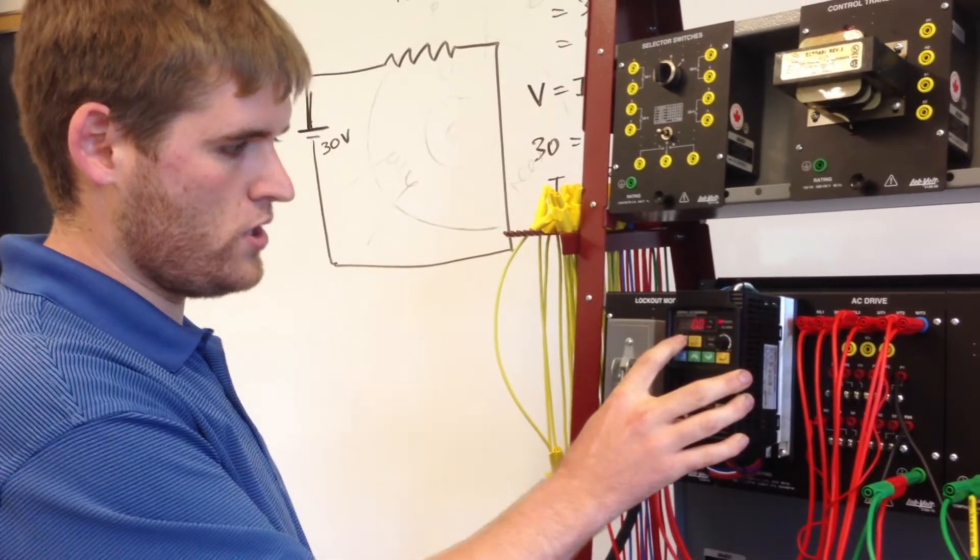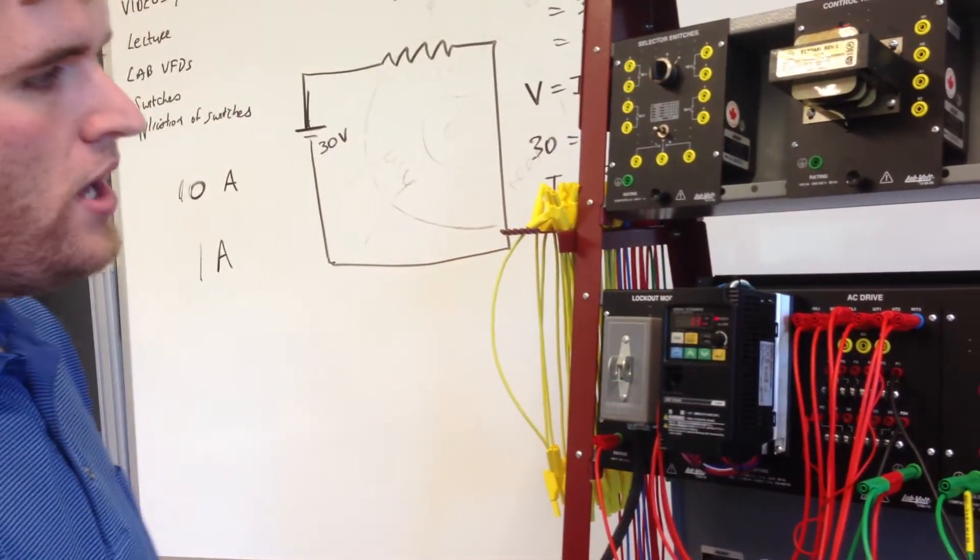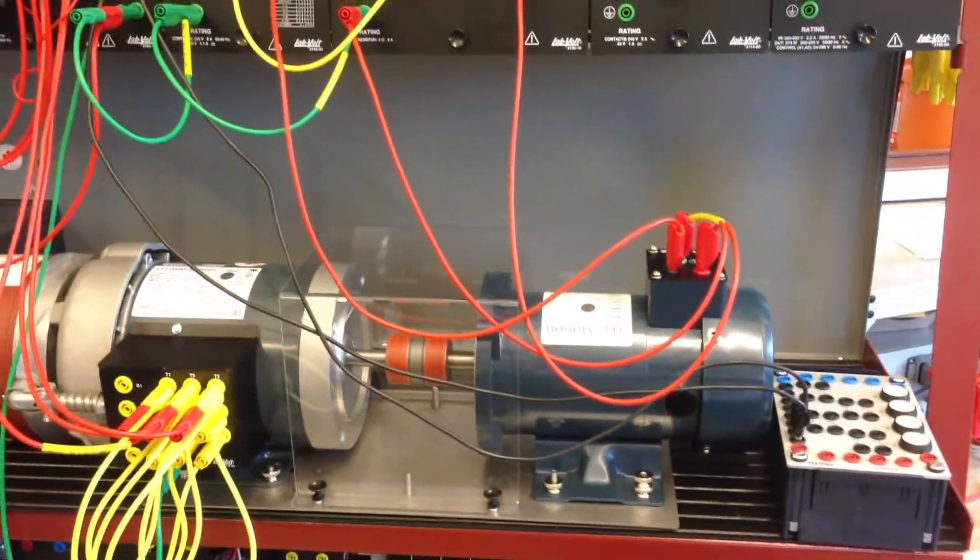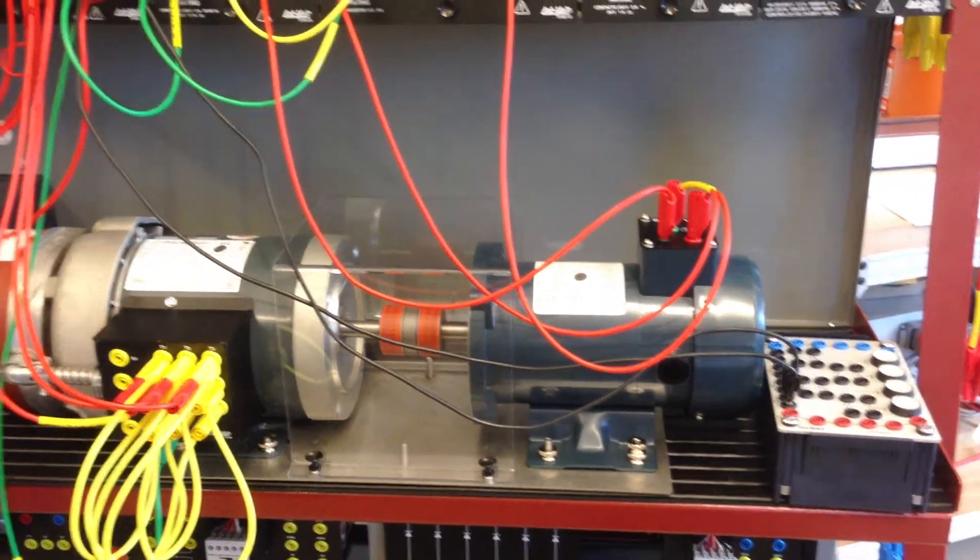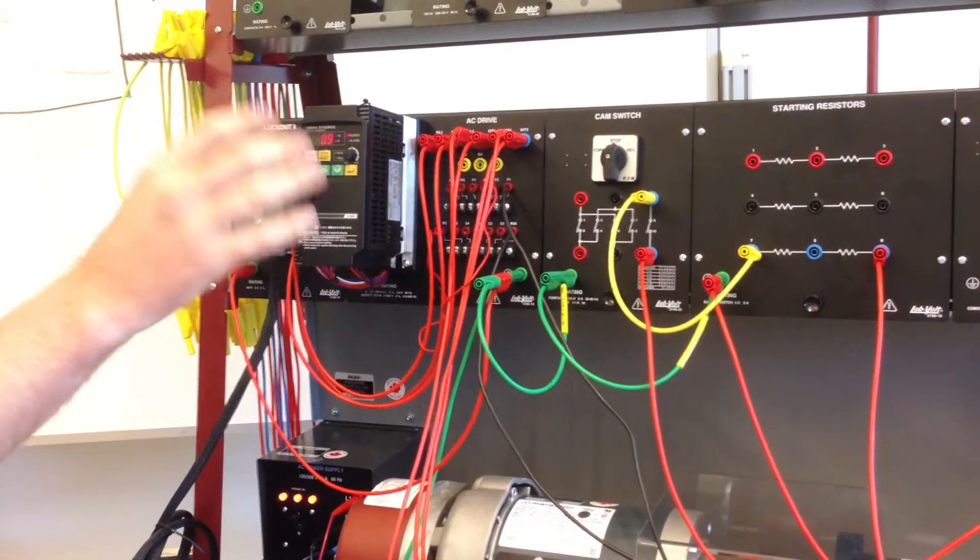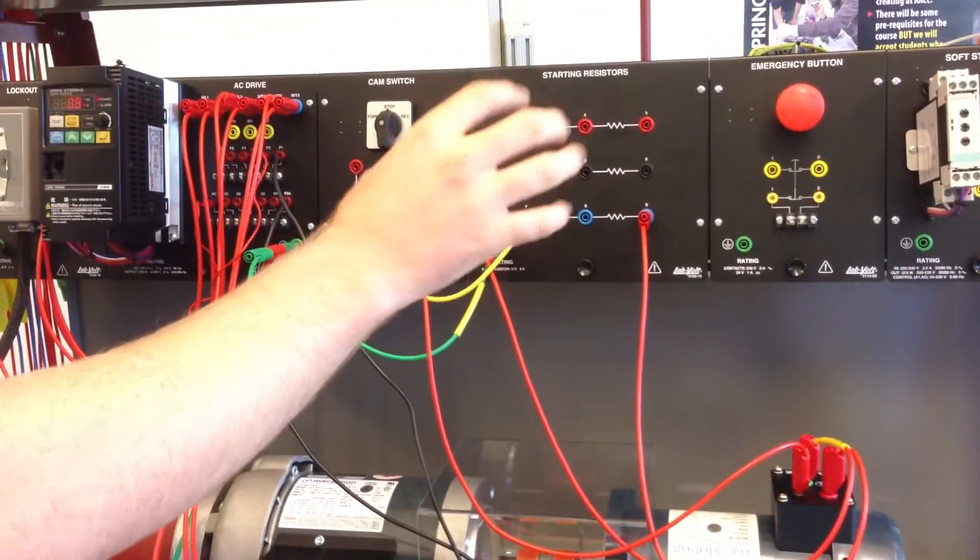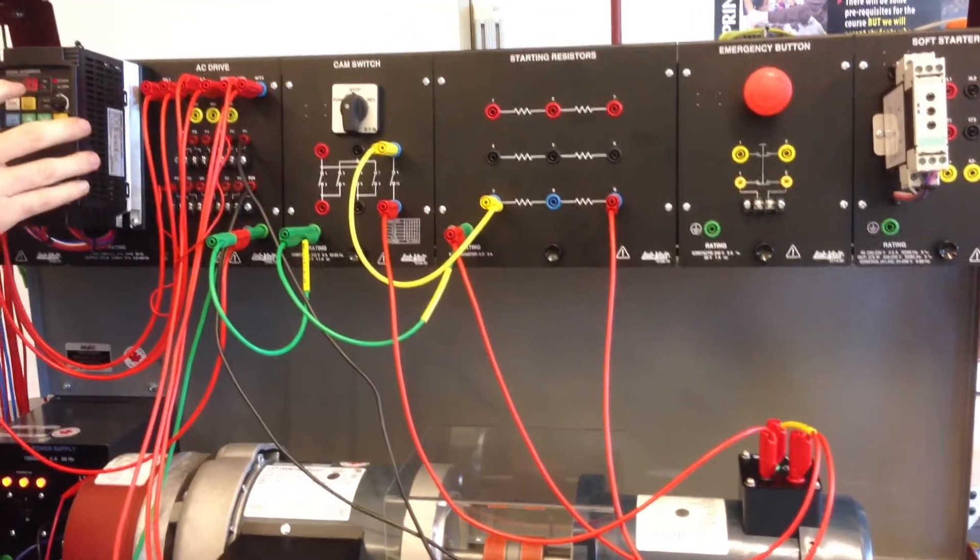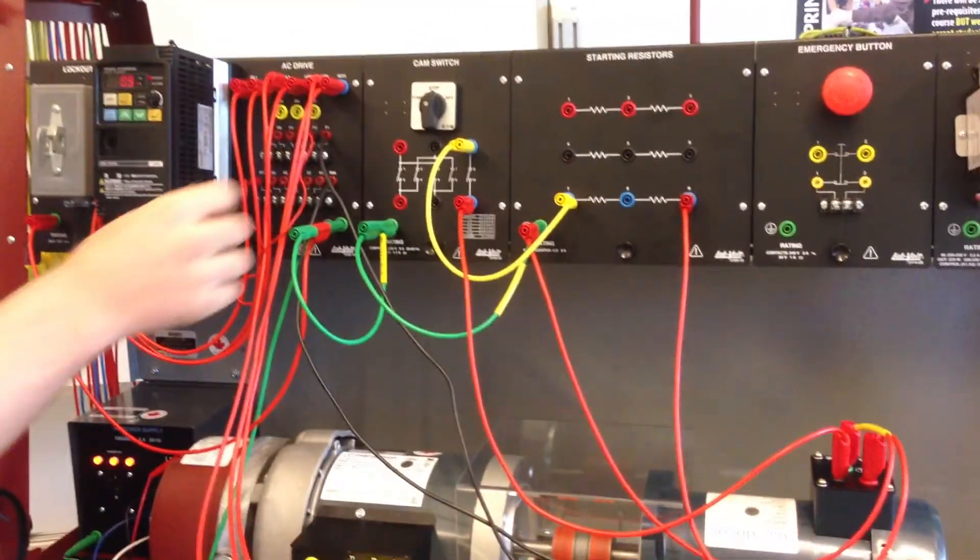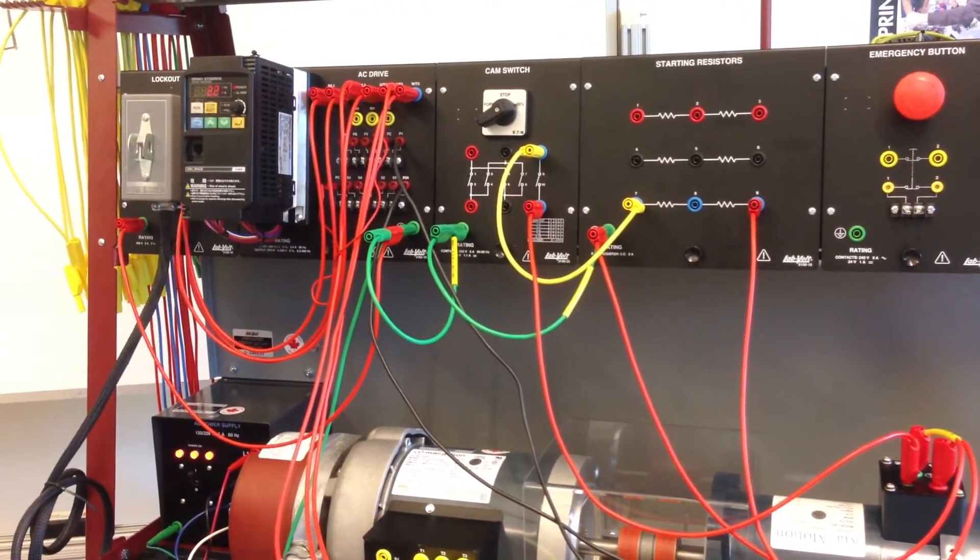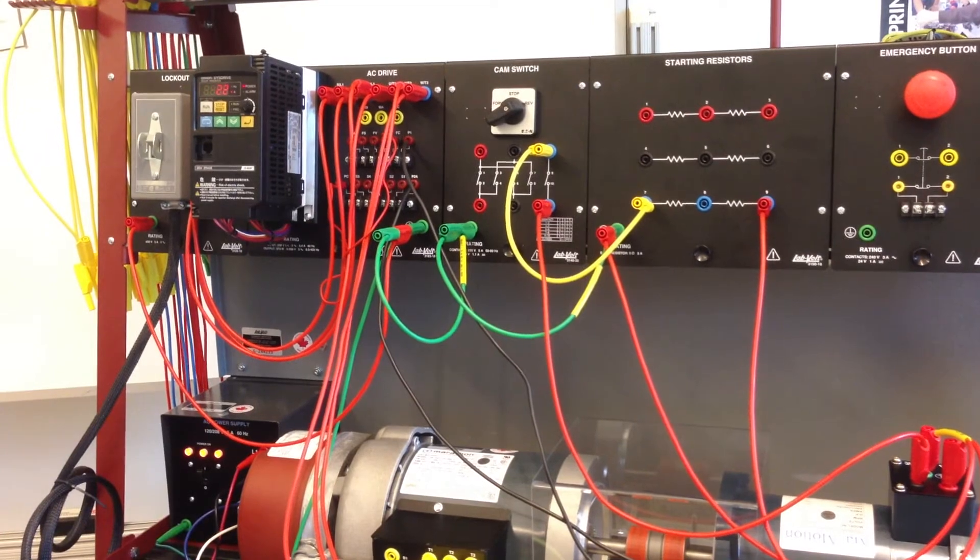Alright so let's go ahead and run this. And right now I have my cam switch set to stop so there's no load on the DC motor. So it's going to spin up to about 60 hertz which is the maximum our VFD can output. And you can see here that our draw is 0.9 amps. Now what I'm going to do is I'm going to switch my cam switch which is going to put this resistance on this DC motor. And then we're going to watch this amperage climb. Okay. And you see right now it's reading 2.2. Like I said my B22 setting is set to 2.1.